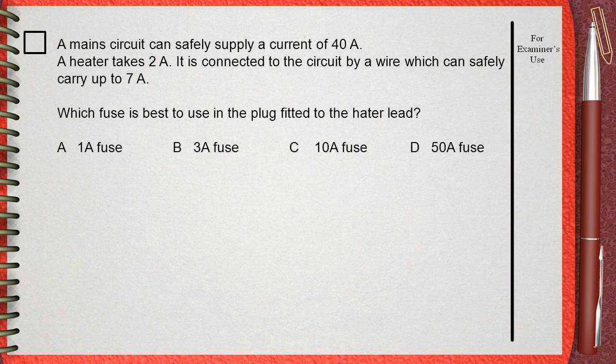We protect the heater itself. That's why when we choose a fuse, we don't care about the 40 Amperes of the supply or the 7 Amperes that can be carried by the wires. We are protecting the heater, so we only care about the 2 Amperes taken by the heater.